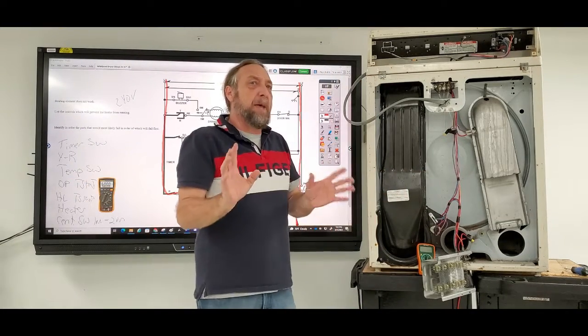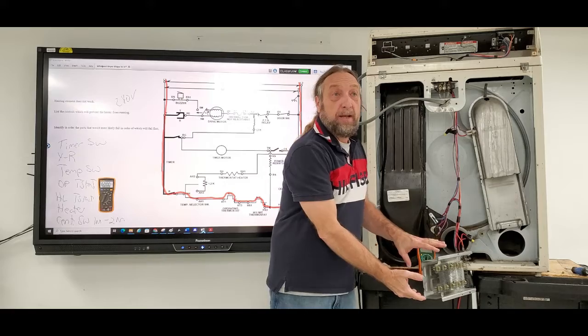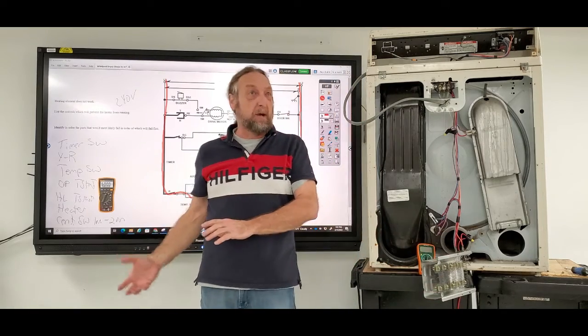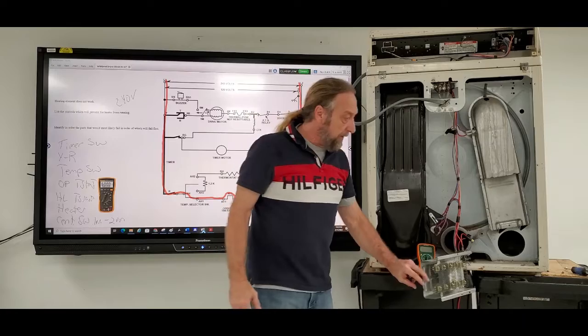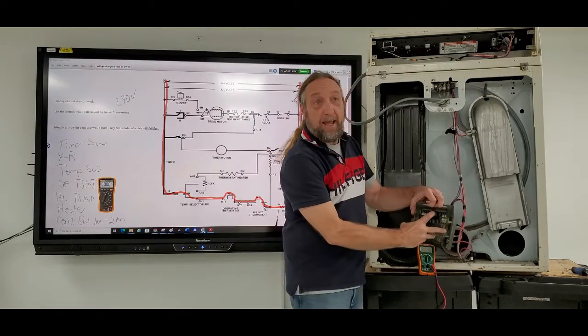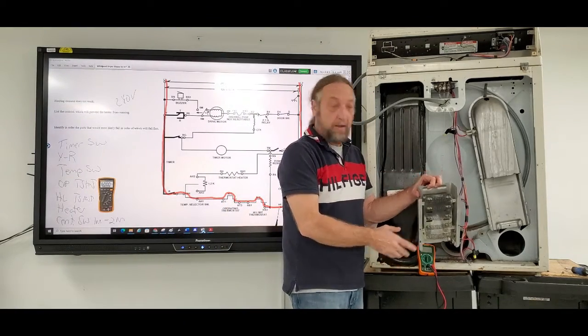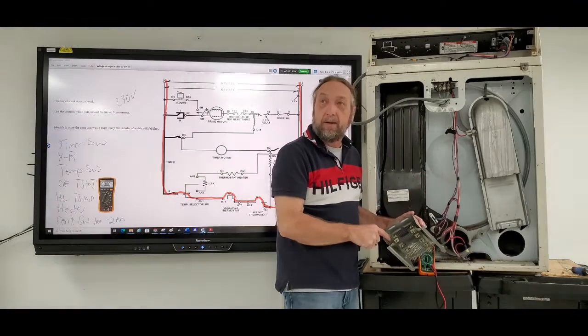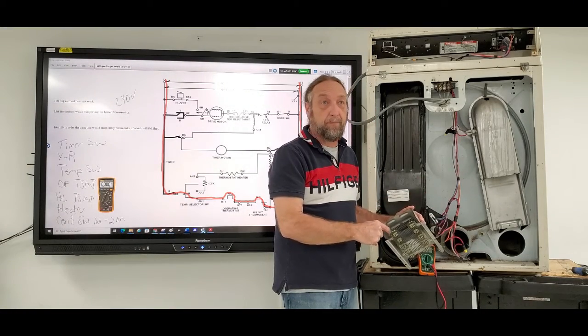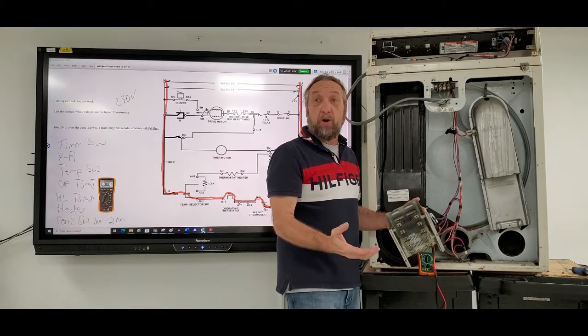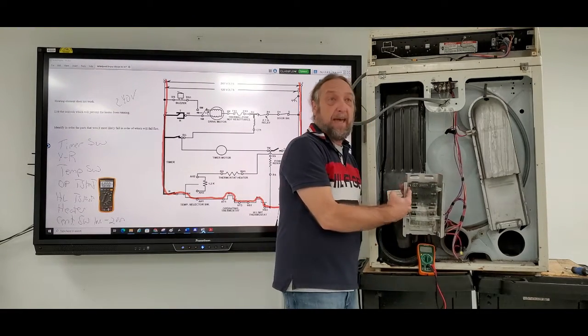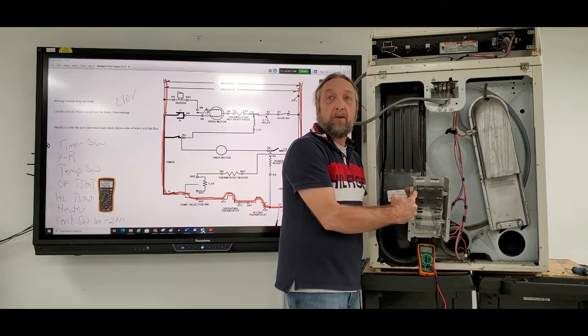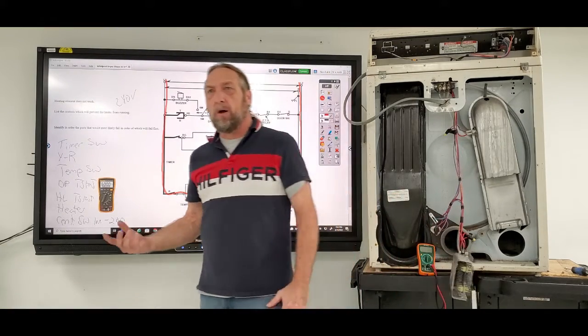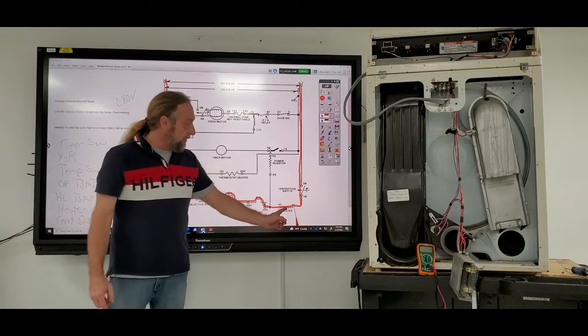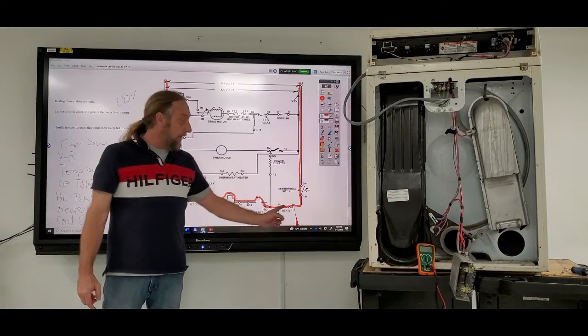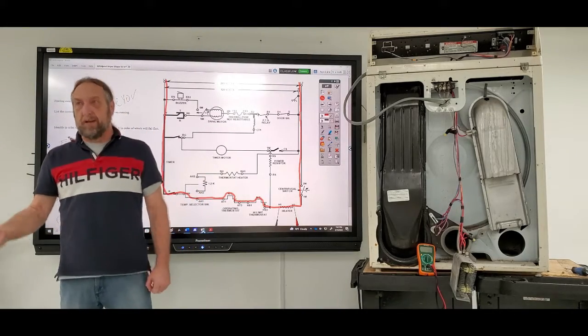So Whirlpool decided, let's make a change and let's make this shorty heater where they just pull this off and replace this, and now we got a heater. But the problem is the heater was on this side and the other side of that metal divider. And right here at the top, the heater crossed over. And if the customer had poor airflow, that wire would sag and touch the metal here. And you say, wow, if it touched the metal, it's going to blow up. But it would touch the metal right in the center of the heater. And so half of the heater would get voltage all the time.